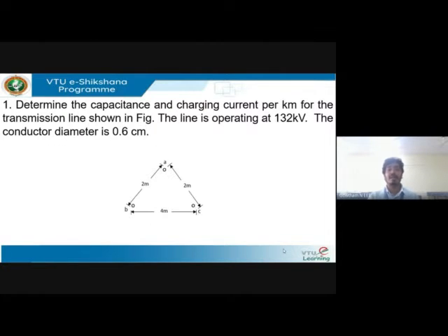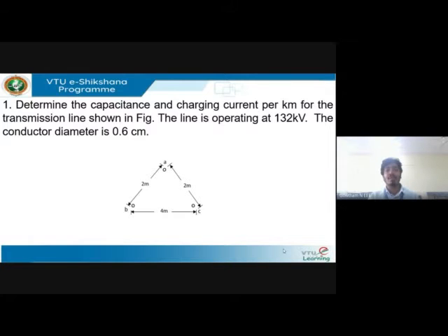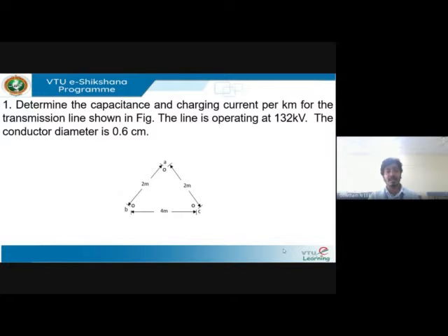Let's get started with the first problem. You will be asked to determine the capacitance and the charging current per kilometer for a transmission line shown in the figure. The line is operating at 132 kV and the conductor diameter is 0.6 centimeters. From the diagram, the distance between conductors A and B is two meters, between B and C is four meters, and between A and C is two meters.